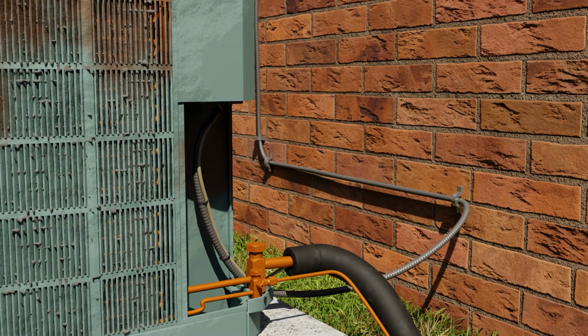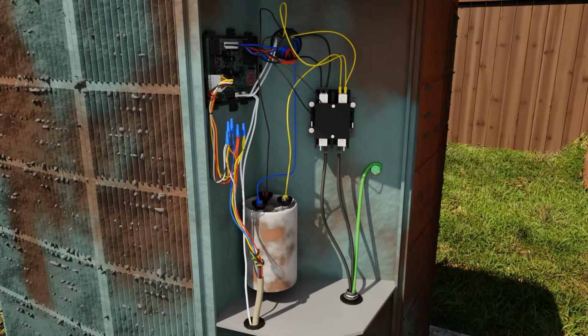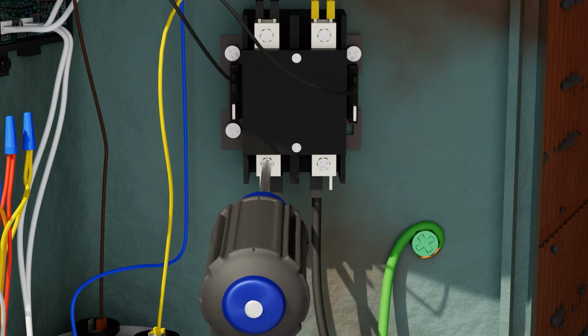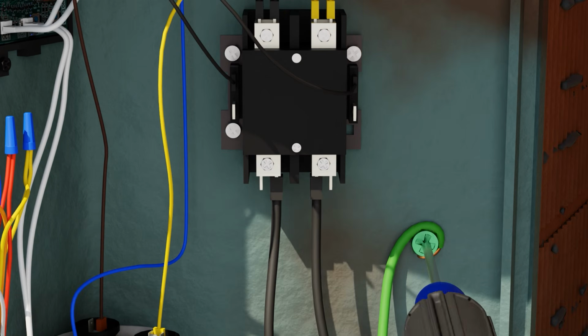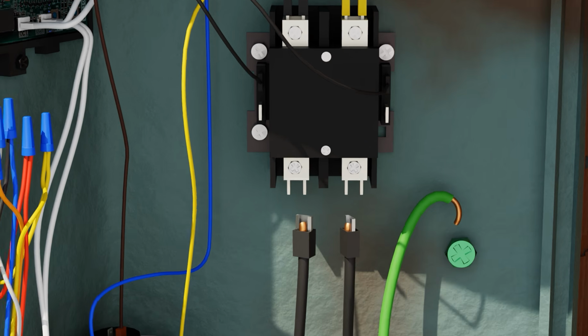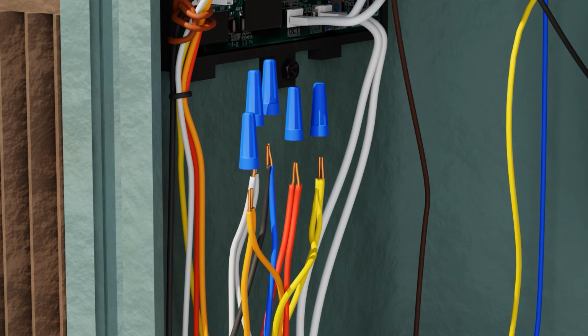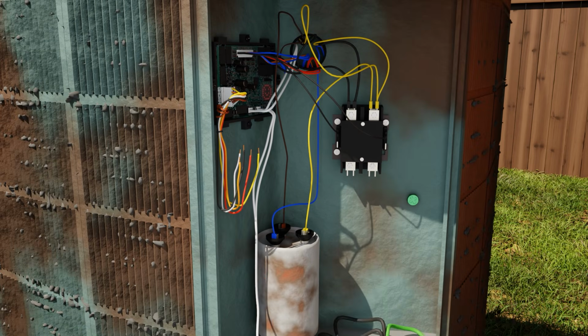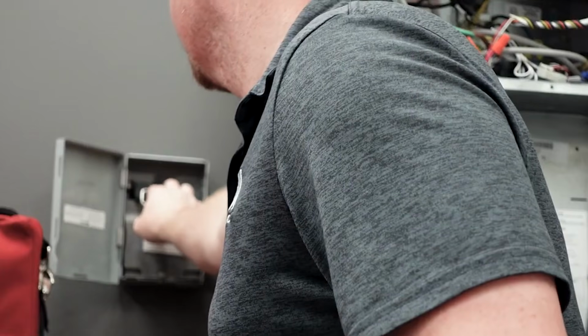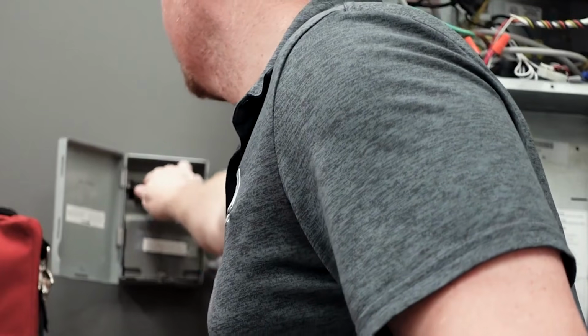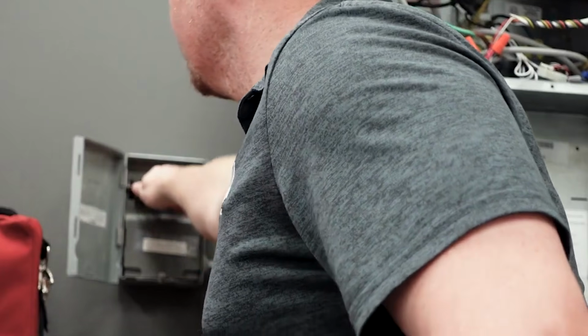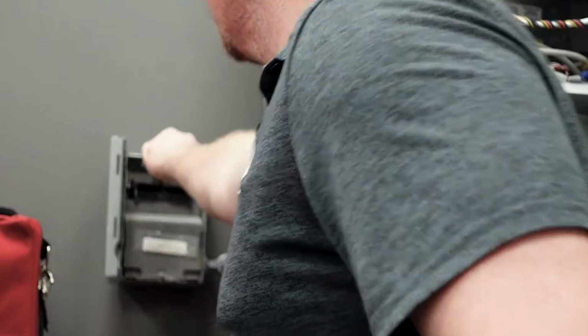Now begin disconnecting all of your electrical connections. At this point, you would have already tested to make sure that everything is electrically turned off by testing from leg to leg and leg to ground as shown before. Before you disconnect your low voltage on the outside, you would also want to make sure your disconnect is turned off to the inside unit, your furnace or your air handler. That way you won't create a short circuit on your low voltage controls.